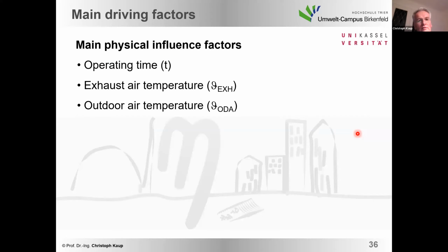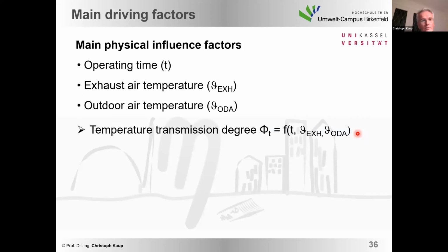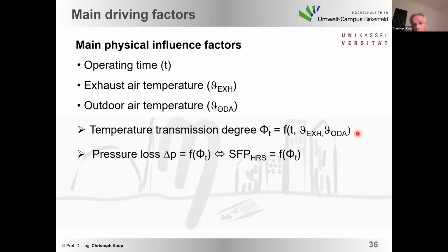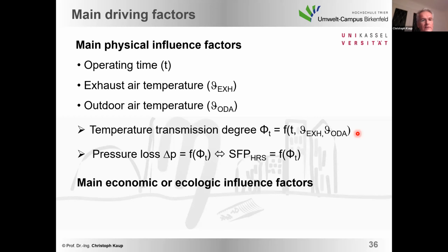And the temperature difference is given by the exhaust air temperature on top and the outdoor air temperature on the bottom. And the difference is the driver of the heat recovery, as well as the operating time, same influence as you already saw. And that will lead to the optimum temperature transmission or efficiency, which is a function of all the three. And this transmission degree is determining at the end the pressure loss or the SFP value, which is nothing else than the pressure loss related or divided by the efficiency of the fan system.